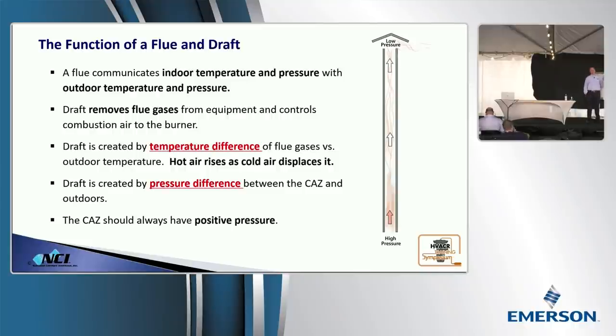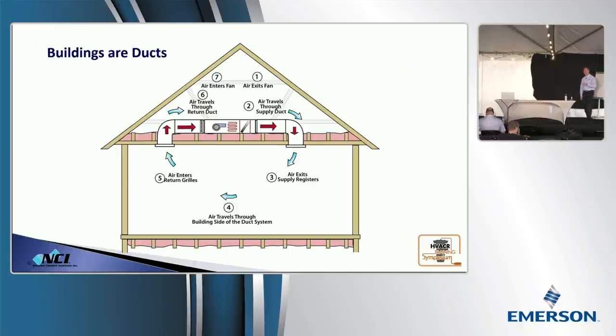And the combustion air duct, oh, air comes down that one. But there's some driving forces that affect that. Now, buildings are ducts. When you look at this, we've got just a nice standard building, furnace up in an attic. We're going to assume it's a perfect duct system. Everything's sealed, airflow's balanced. All the air that's going into the duct system is coming out. All the air that's being delivered into the building is coming out. We've got nice, solid flow moving through there.